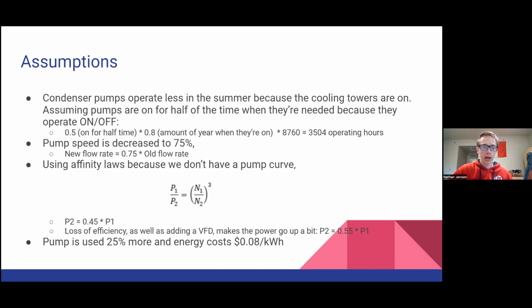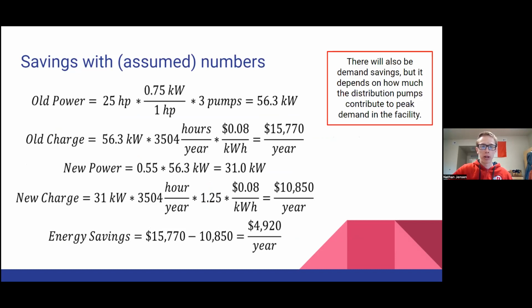So if we go to the next slide, we show you some dummy calculations we put in. Here we have our 3 pumps. I think there are 2 main pumps, and then maybe there's one for backup. So if you have the 3 pumps in there, convert it to kilowatt hours, you can solve for the current charge. And then if you have the new power, you can solve for the new charge. And as you can see at the bottom there, you save about $5,000 a year. And it's quite possible there would be demand charge savings, but we don't know that. And so we put that here on the slide.